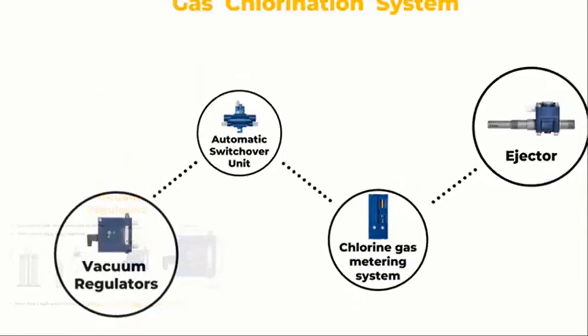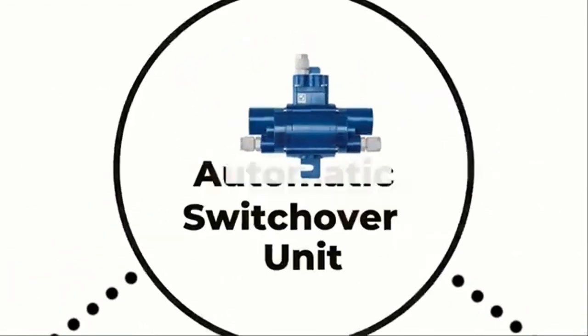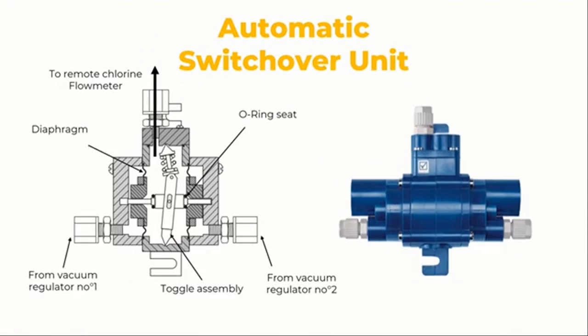The switchover system is the second element. For continuous chlorination, it converts the chlorine supply from an empty chlorine source to a full chlorine source. It's entirely vacuum operated. The wall-mounted automated vacuum switchover module must be toggle operated and spring loaded. The switchover components are made of molded plastic that can be used with wet or dry gas, and all of the springs are made of tantalum alloy.